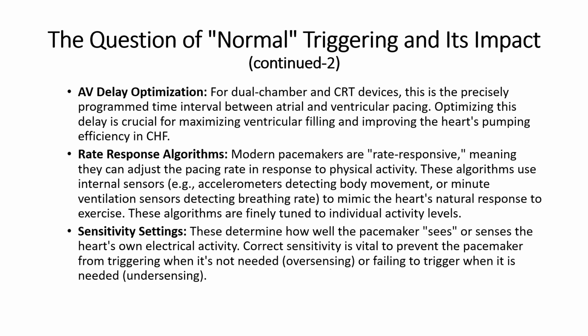AV delay optimization. For dual-chamber and CRT devices, this is the precisely programmed time interval between atrial and ventricular pacing. Optimizing this delay is crucial for maximizing ventricular filling and improving the heart's pumping efficiency in CHF. Rate response algorithms. Modern pacemakers are rate responsive, meaning they can adjust the pacing rate in response to physical activity. These algorithms use internal sensors, e.g., accelerometers detecting body movement, or minute ventilation sensors detecting breathing rate, to mimic the heart's natural response to exercise. These algorithms are finely tuned to individual activity levels. Sensitivity settings. These determine how well the pacemaker sees or senses the heart's own electrical activity. Correct sensitivity is vital to prevent the pacemaker from triggering when it's not needed, oversensing, or failing to trigger when it is needed, undersensing.